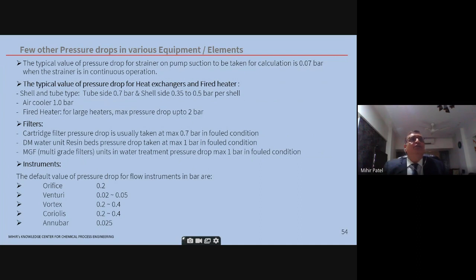Heat exchangers, tube side normally 0.7 bar. Shell side you can keep lower, 0.35 to 0.5. Air cooler 1 bar. Fired heaters you can go up to 2 bar through the coils. Filters normally 0.7 bar. Resin beds and multi-grade filters for water services you can take up to 1 bar. Instrumentation, as you can see, these are the varying pressures which normally one takes in the hydraulic calculations.